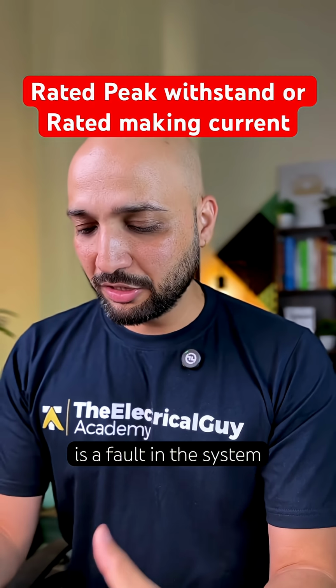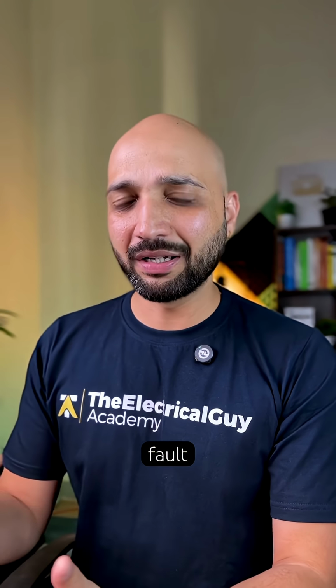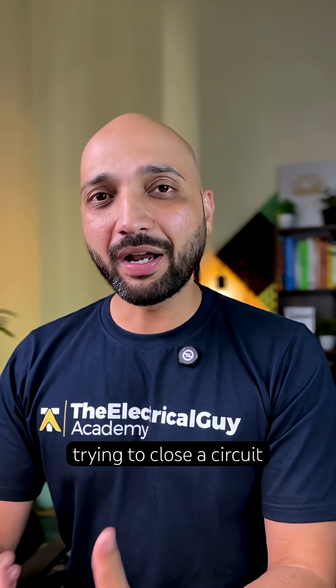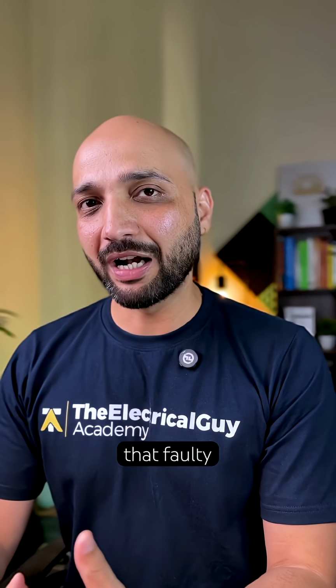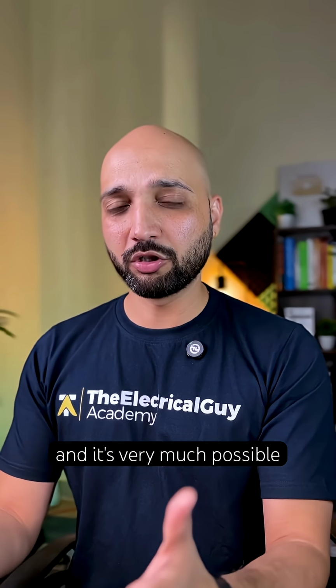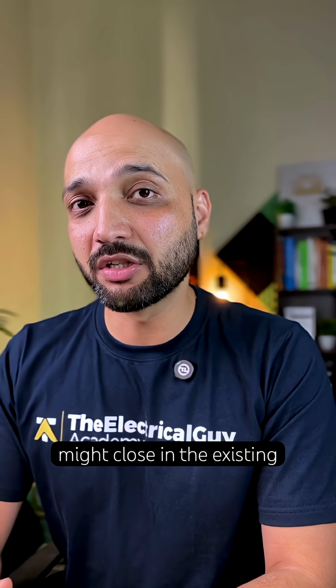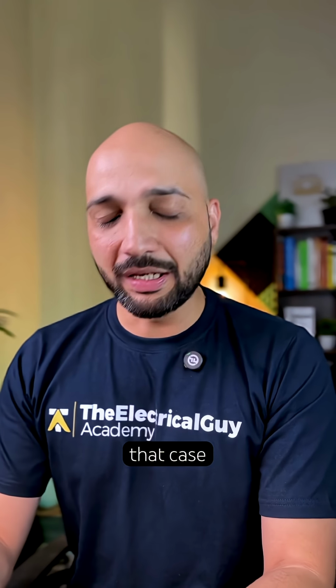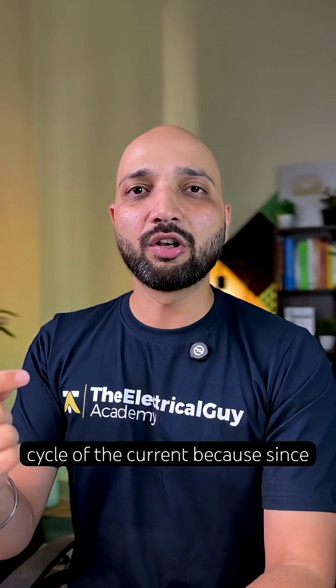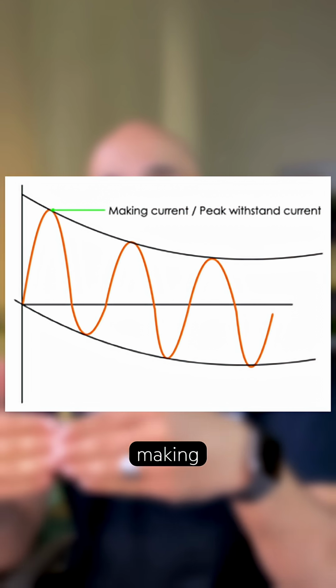Now imagine there is an existing fault, an existing short circuit in the system, and you're trying to close a circuit breaker during that faulty condition. It's very much possible that the breaker might close into the existing fault. In that case, during the first half cycle of the current, since the contacts of the breaker are closing or making, the short circuit current can go to a very high level, and that is what we call the making current or the rated peak withstand current.